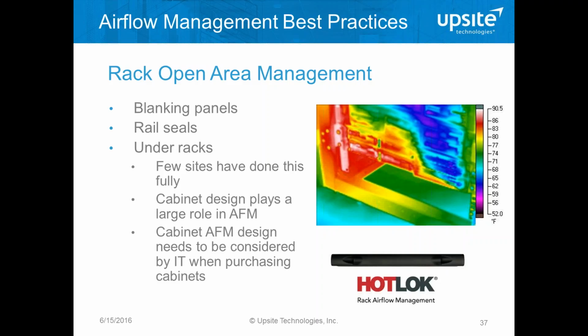We see here in this image that the bottom 2U in this cabinet and the left 2/3 of that equipment is receiving very high intake temperatures, and that's the result of just missing blanking panels in the bottom 2U, as well as openings between the rail and the side of the cabinet. And blanking panels, the ones that we've designed, are in our HotLok family line of products, and those installed in the space would block that airflow and solve the hotspot, the high intake temperature problems, with no other adjustments necessary.